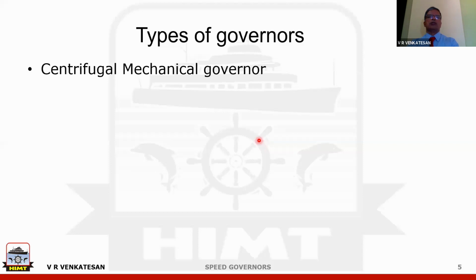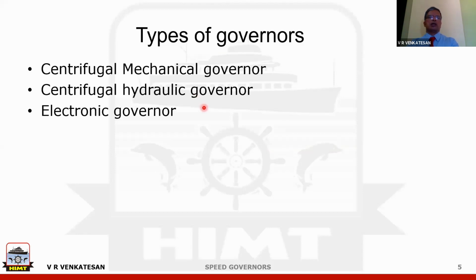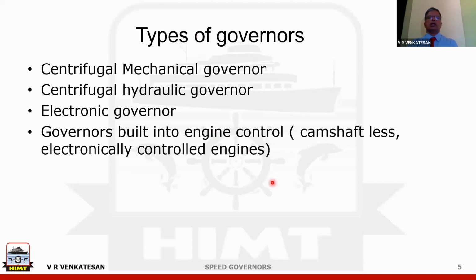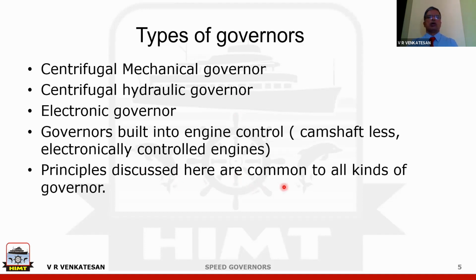There are centrifugal mechanical governors, and centrifugal hydraulic governors. Electronic governors are there, and you also have governors which are built into the engine control. That means it will not be identifiable separately as a governor. So in these modern camshaftless and electronically controlled engines, the governor is not a separate discrete equipment. It is built into the engine control. Our main discussion is on the hydraulic governor, for the sake of understanding the mechanism. But whatever principles are discussed here are common to all kinds of governors. The principles of droop, compensation, sensitivity and similar things apply to all kinds of governors. The method will vary from type to type.